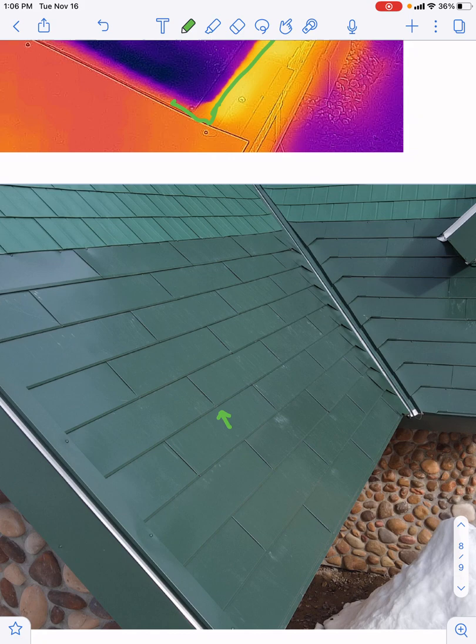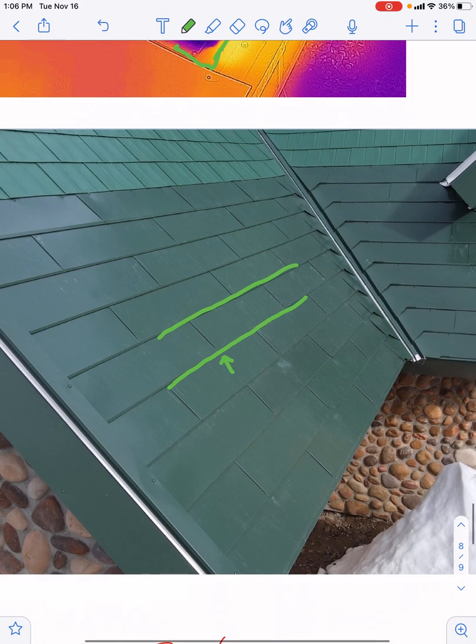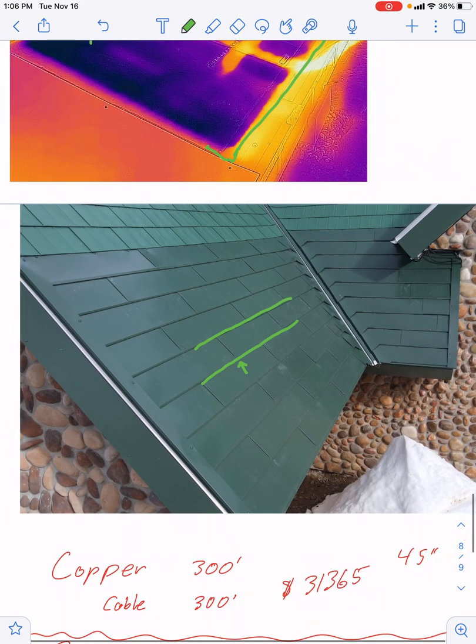The cable actually slips right into the lip, so it can come out and it can go back in, but it's pressurized in that cavity along each row, allowing the heat to transfer into the metal. So that pressure is key in the performance. But the advantage of this whole system is that you can get to the cable when it goes bad. So if you put a roof on and the copper or steel plates, 50 years from right now, you may need to replace the cable a couple of times, and you don't have to replace the whole roof to do so. So that's one of the advantages.